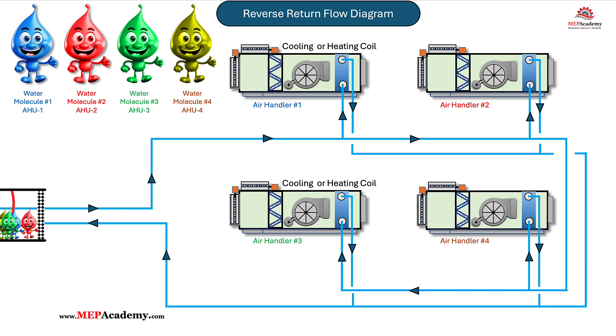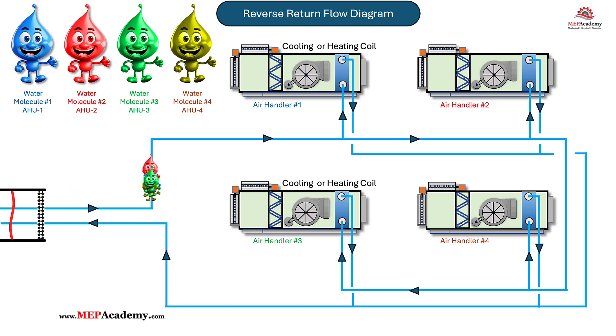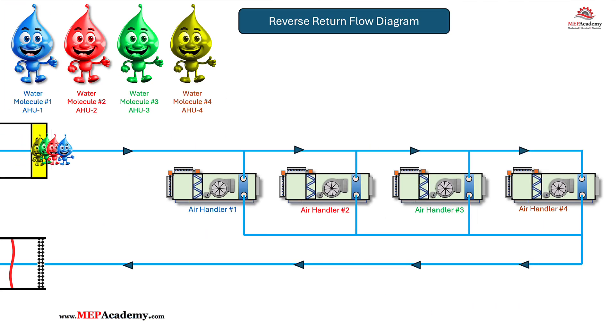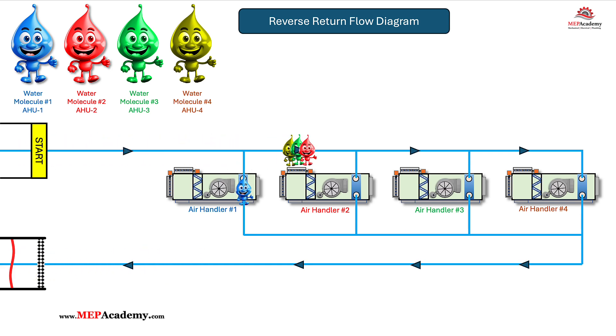The theory is that each air handler will have the same distance from the source and back, which would make their pressure drops equal and balancing valves not required. In theory, maybe — but air handler zone differences can affect the pressure drop through each coil as each control valve adjusts flow for its current zone demand. All the water leaving the chiller will return from each air handler at approximately the same time, as the total round-trip piping length is the same distance. The water for each air handler arrives at different times, but the total length is the same overall, which balances out the pressure drop in a perfect world.